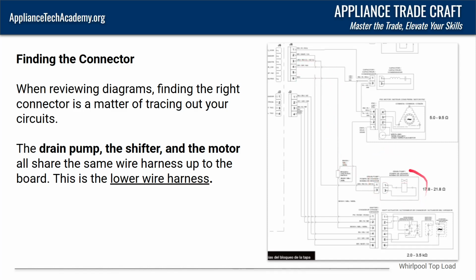That's how easy it is to use a wiring diagram to figure out how to test a load and how it gets this voltage. Now the cool thing about this is we don't need to tip the unit back, pull the connector off, get a resistance reading across that. We can do it right from the control board at those two test points. We can disconnect that connector and check resistance.